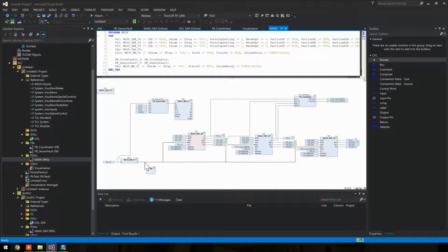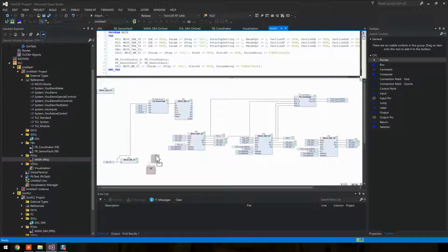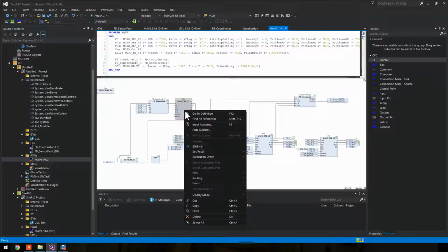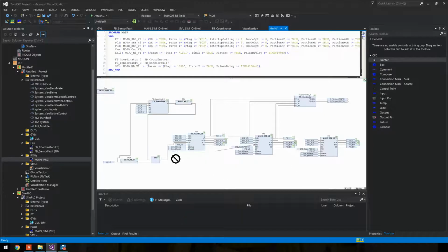Now we will be having two faults into one OR for the safeguarding. So if we didn't have the option of blocking in each individual alarm, we could only block on the SPE template and we would block everything. But now we can block each individual alarm if we want, and we can block all of them if we want to do that. Then add it to the others.